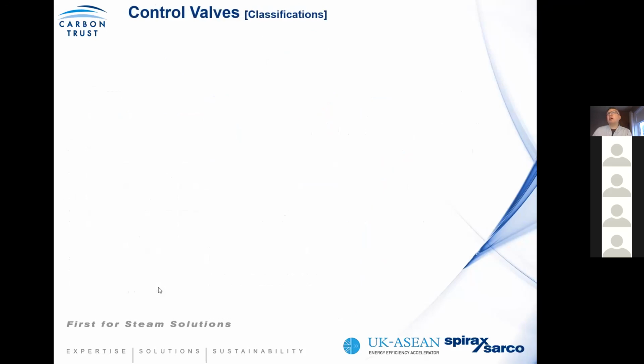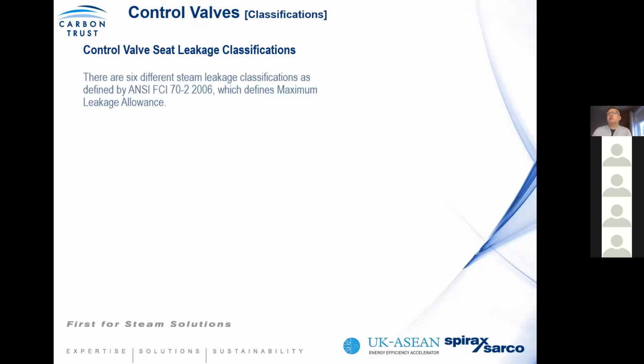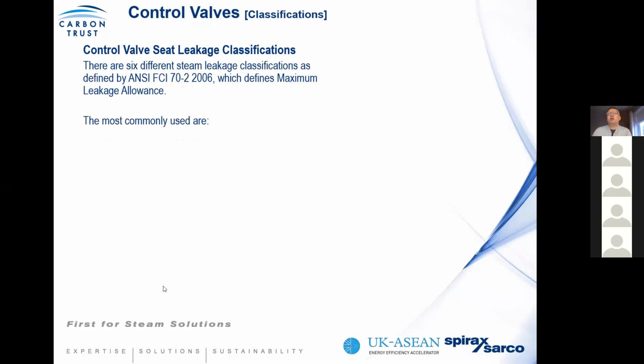Next, we're going to look at control valve classification. So we talked about the distribution system and getting high quality steam to the end user. Now let's consider simple things like control valve classifications. When we look at the type of control valves which are commonly installed, although you have 6 classes, the 2 most common ones in use are the class 4 valve, which is normally referred to as a metal to metal valve, and the class 6 valve.